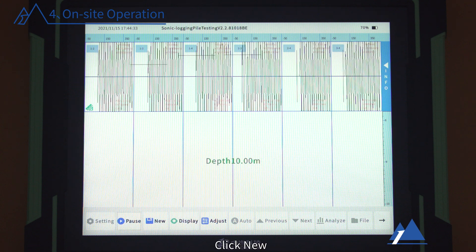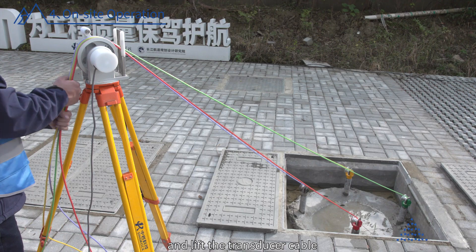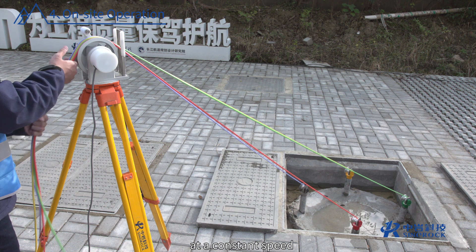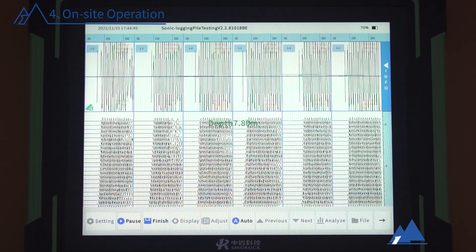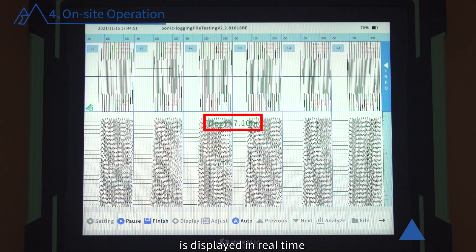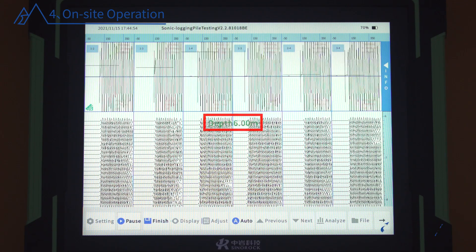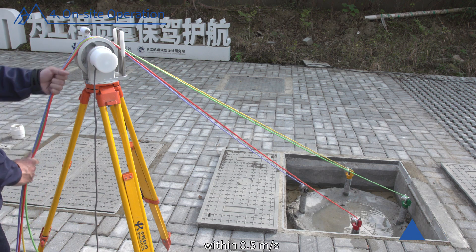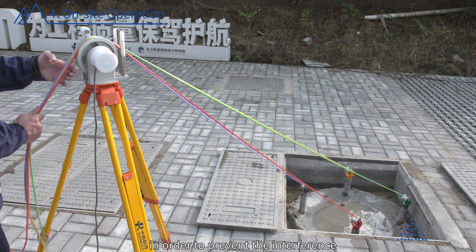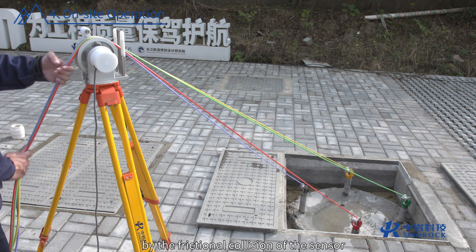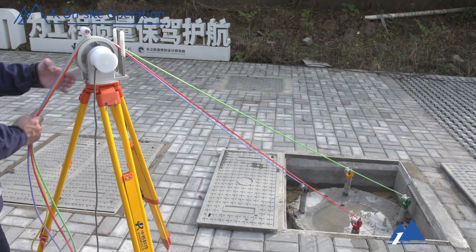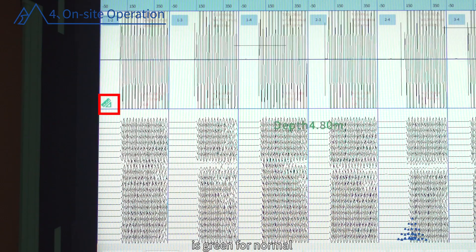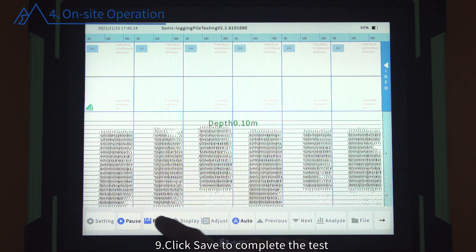Start Test: Click New, enter the file name, and lift the transducer cable at a constant speed until the transducer reaches the nozzle. The current sampling depth is displayed in real-time as the transducer is raised. The lifting speed should be controlled within 0.5 meters per second to prevent waveform interference issues caused by frictional collision of the sensor and the acoustic pipe. The speed indicator is green for normal and red for too fast, indicating the possibility of missing data points. Click Save to complete the test.